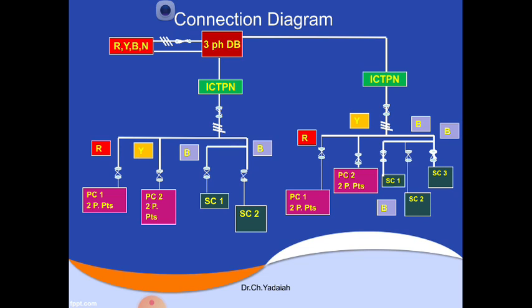After that we are going to calculate the length of the conduit. The length of the conduit depends upon the place where we are going to provide the points, bulb points, fan points or tube light points. As per IE rules, the switchboard should be provided above 1.5 meters, and the horizontal run should be 0.5 meters from the roof, and the DB, the distribution board, will be placed at 2.75 meters from the ground. We have already seen these as per the IE rules. Based on this, we are going to calculate the horizontal length, the vertical up and the vertical down.